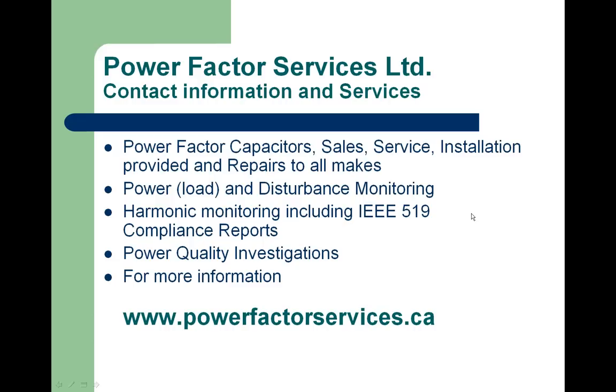In cases of IT farms, certainly harmonic filters are necessary. As you saw in the earlier slide, that is the effect of having conventional capacitors. Utilities won't be reducing their capacitor switching in the near future. We do a lot of harmonic analysis and power monitoring, and for years we see way more utility capacitor switching now than we did 5, 10 years ago. That's simply because the load has been increasing. The transmission reliability has been decreasing in some cases.